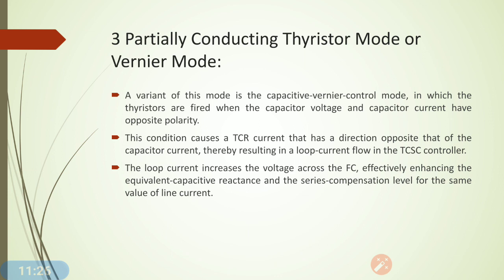One variant of the vernier mode is the capacitive vernier control mode, in which the thyristors are fired when the capacitor voltage and capacitor current have opposite polarity. Due to this condition, the TCR current has a direction opposite to that of the capacitor current, resulting in a loop current flow in the TCSC controller. This loop current increases the voltage across the fixed capacitor and enhances the equivalent capacitive reactance, thereby increasing the series compensation level of the transmission line.